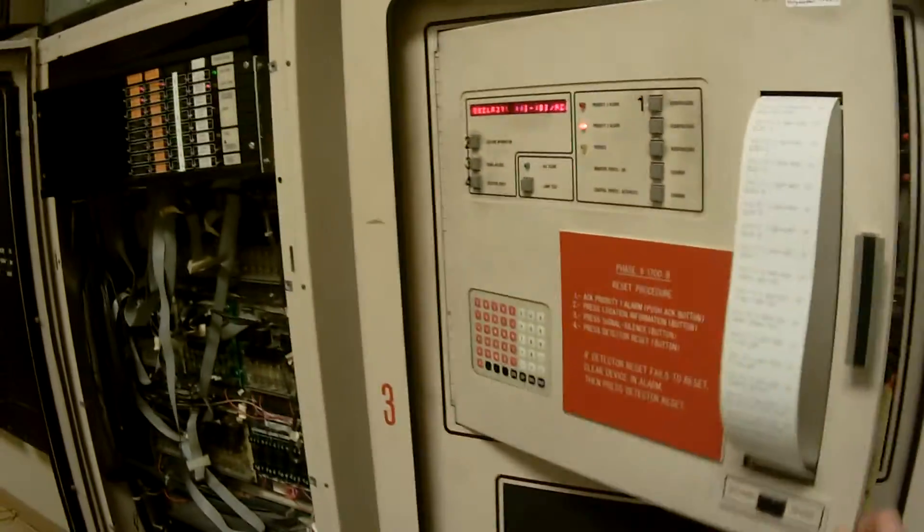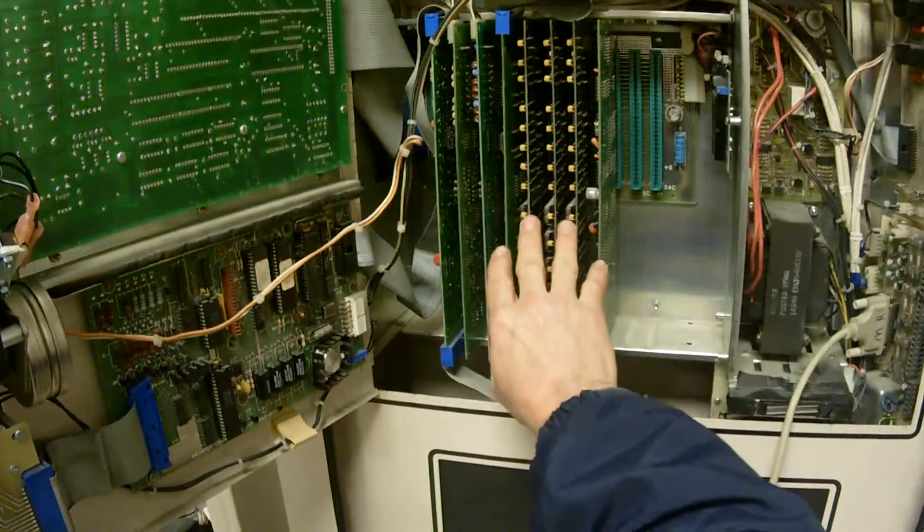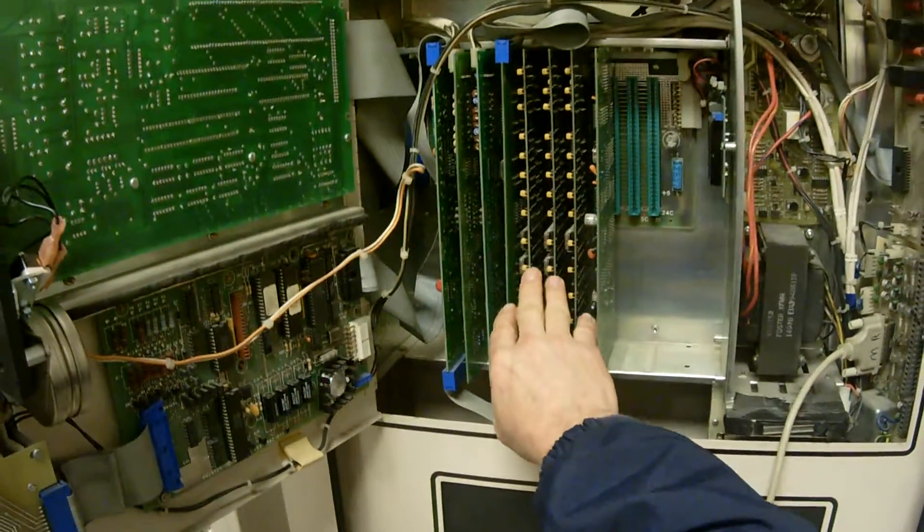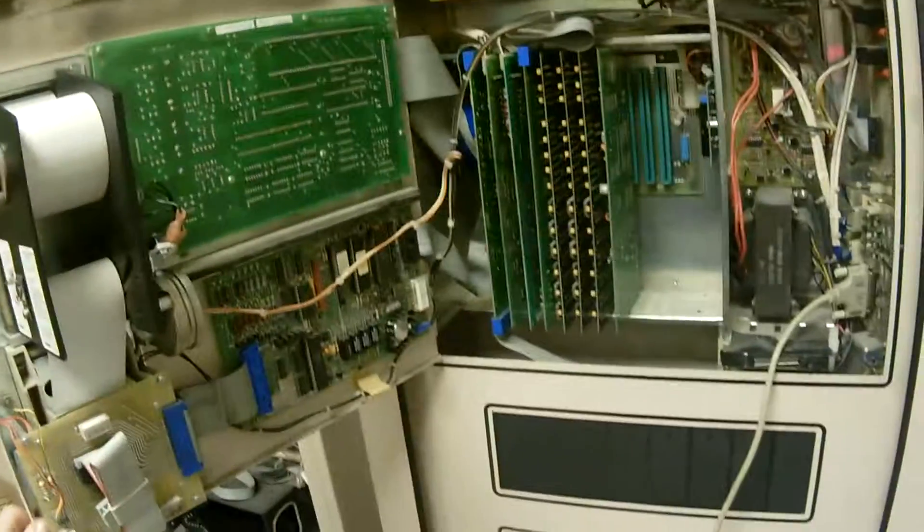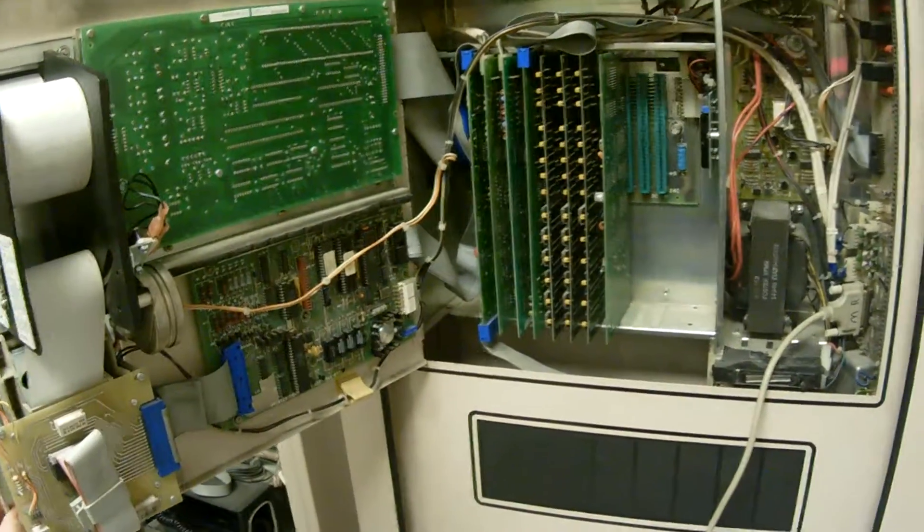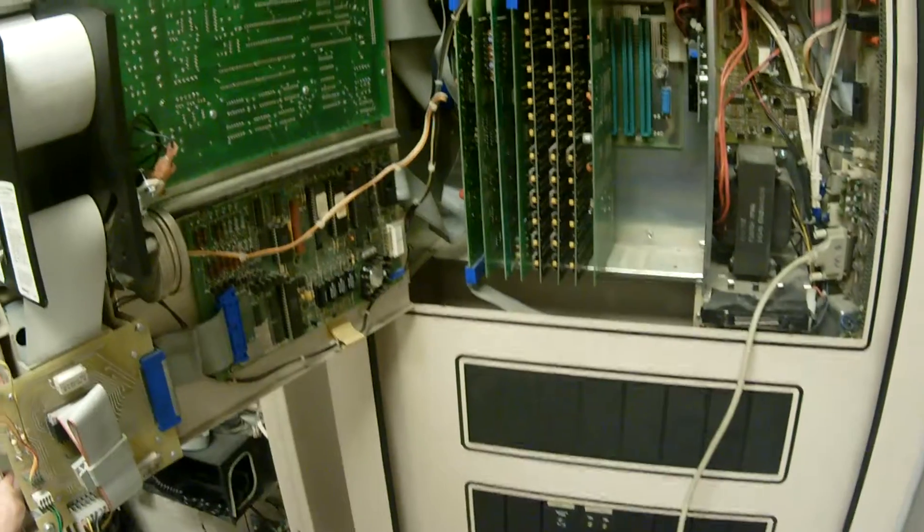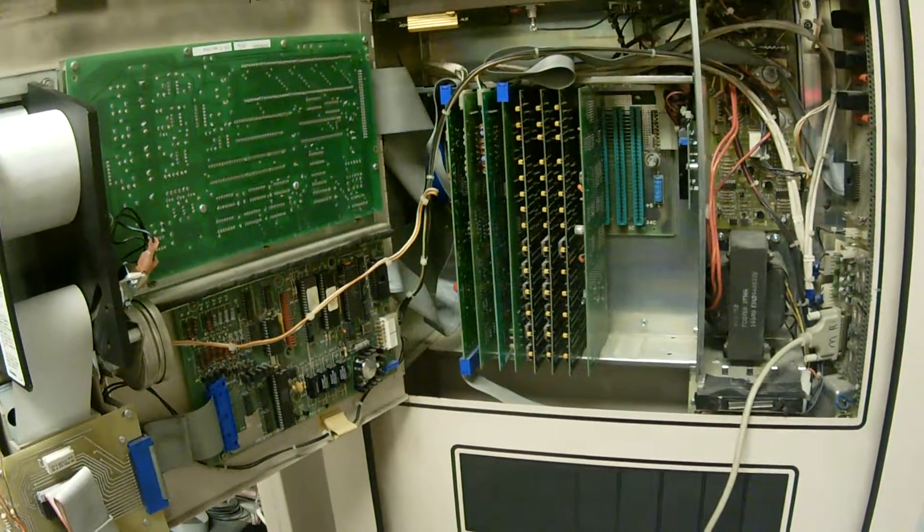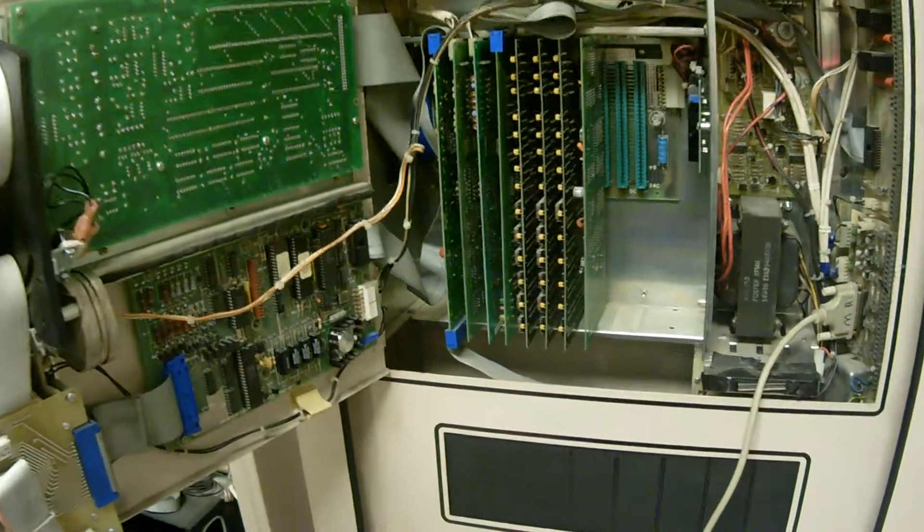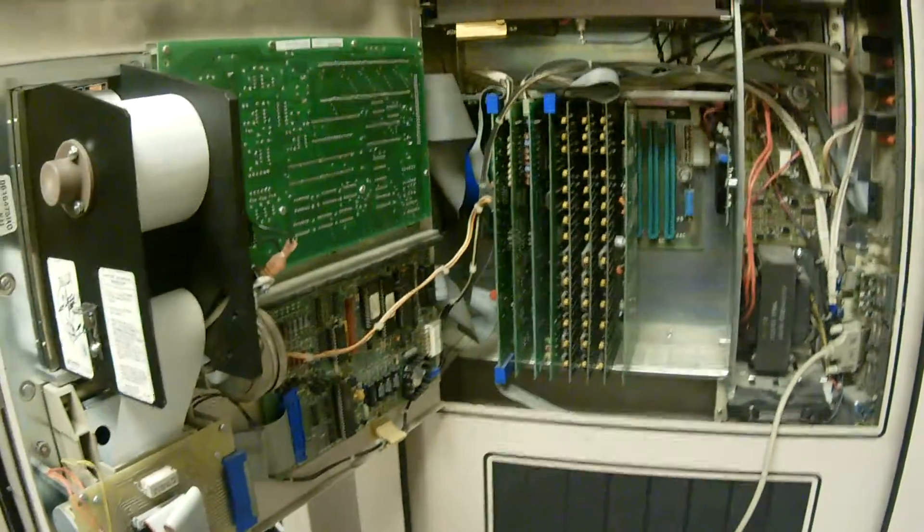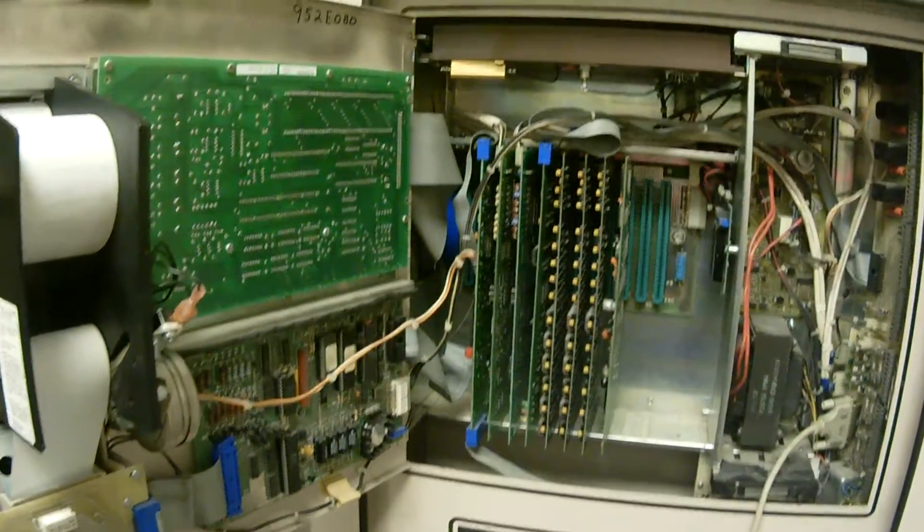When you first turn on this panel, we have these boards here. These are called the PROM boards. All the default programming that was originally programmed for the job site is on these PROM chips here. And when you turn on the panel, what it does is takes all that information from the PROMs and it loads them into the RAM on the CPU board, loads it into the CPU onboard RAM.